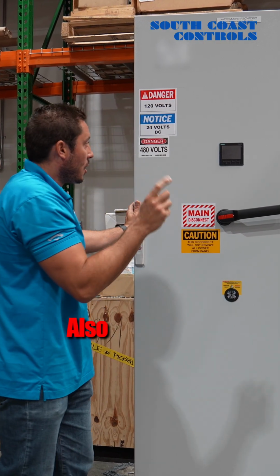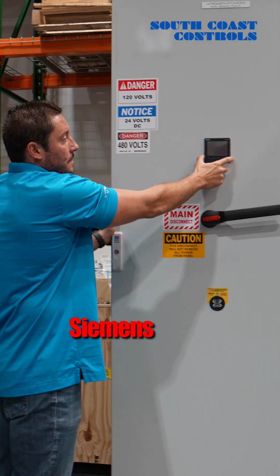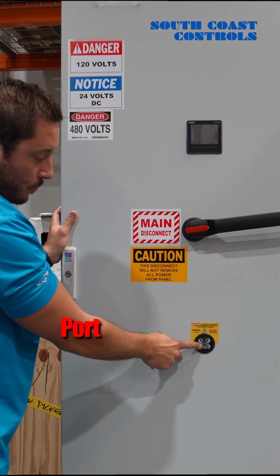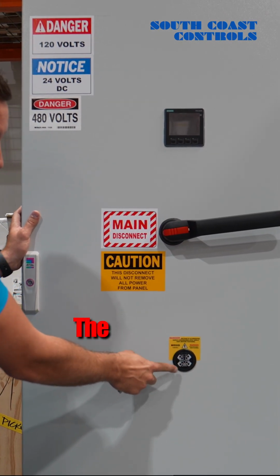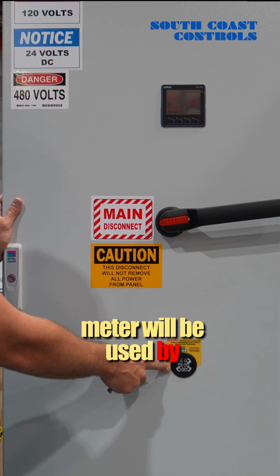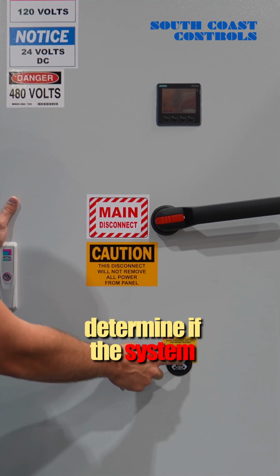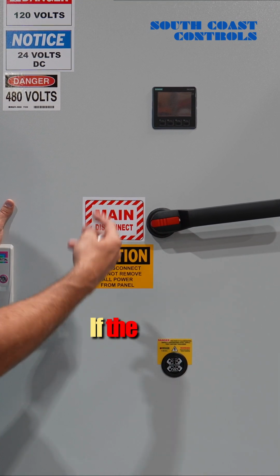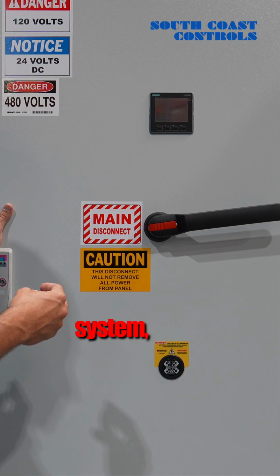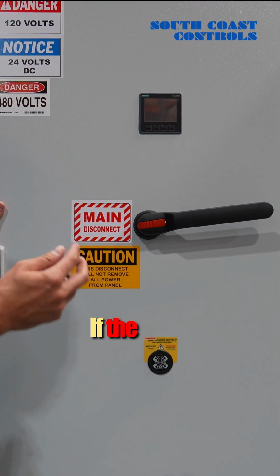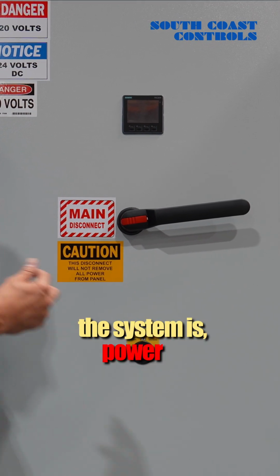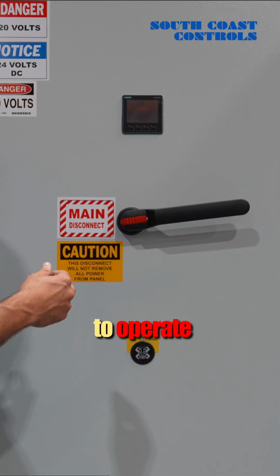breaker. Also on the door of the first bay system is a Siemens meter, and then you'll see a Graceport power meter down below here. The Graceport power meter will be used by maintenance workers to determine if the system is either on or off. If the lights are on, there is power on the system, which means it is not safe to operate. If the lights are off, the power is killed to the system and it will be okay to operate inside. Now let me take you inside the control system.